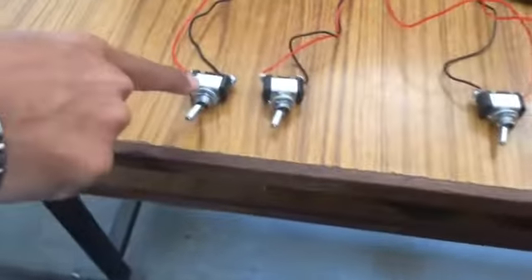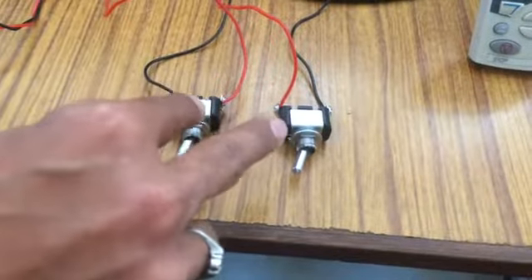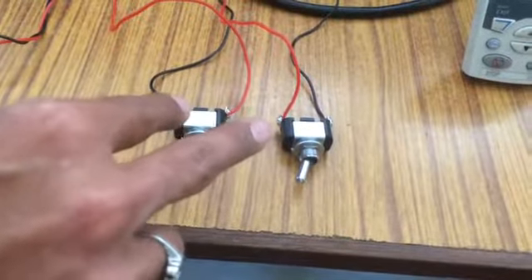Here we have two inputs: one is for run/stop command, another is for forward/reverse command. We have two additional inputs which we are using for preset speeds in binary combinations: 00, 01, 10, and 11.